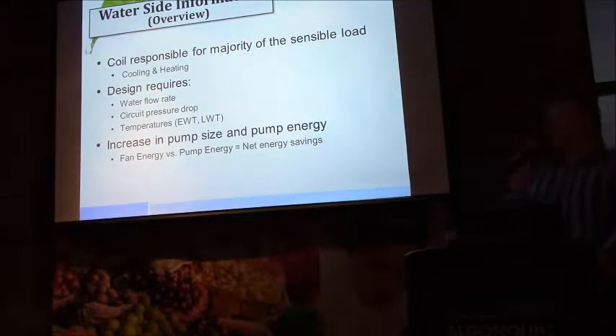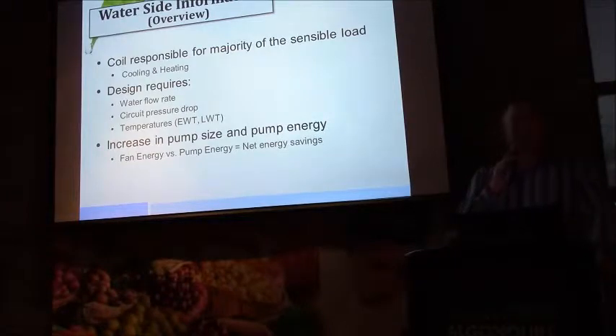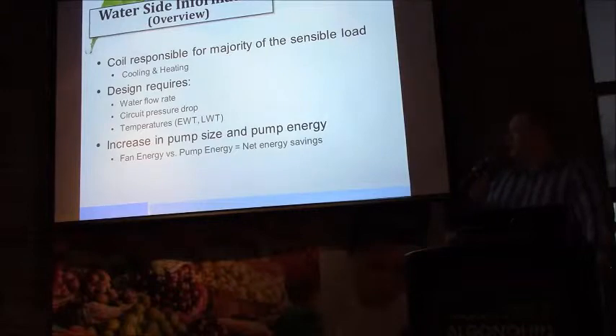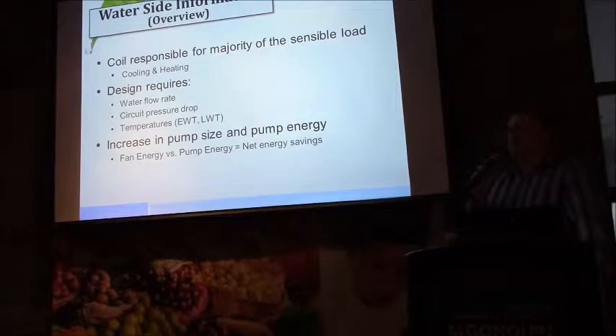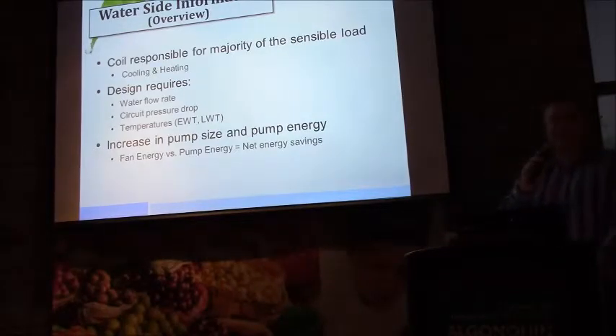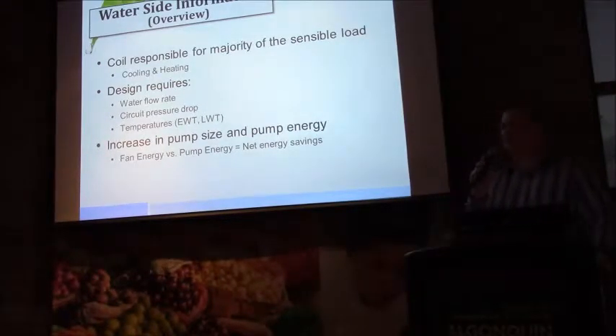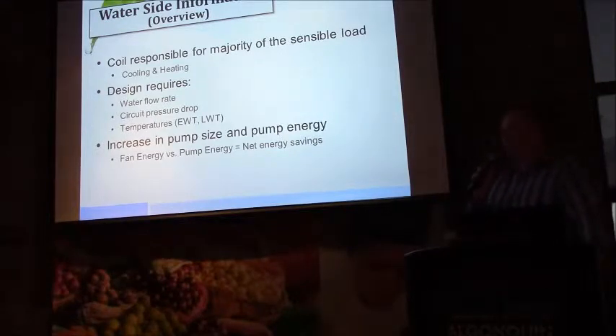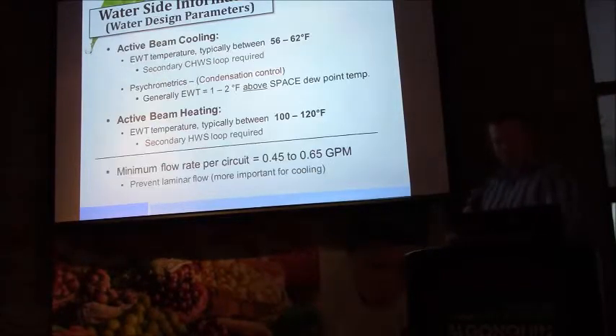But it also has a consequence in the fact that we have to provide more beam, which drives up the capital cost in terms of being able to cool that space. But as a general rule, it's much cheaper to circulate water in the space than it is to supply air. And if we agree to the fact that roughly 42% of the building's energy cost is associated with the air distribution in the space of an all-air solution, anything that we do to reduce the total air volume into the space will translate into real-world savings over the life of the building. Any questions so far?